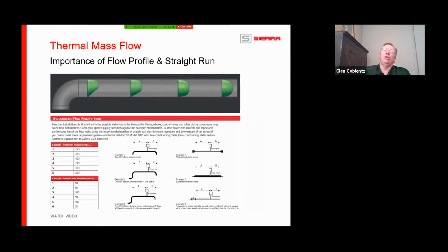Just as a reminder here, we talked about it a little bit earlier, but the straight run of pipe is critical to flow measurement. So don't shortchange that, especially if someone's going to pay $6,000 for a 640i with all the bells and whistles, and they install it 1 diameter downstream of a double 90 out of plane. They're not going to get the result they were hoping for. So this is in every installation manual that we have that you can find on our website. Please discuss this with the customer. Put in the proper straight run of pipe. If you're going to pay that kind of money to make that kind of precision measurement, make sure the pipe is prepared for that.